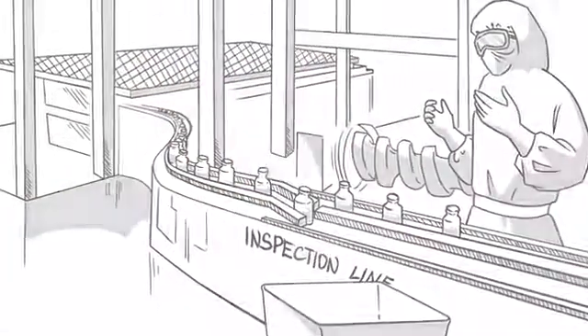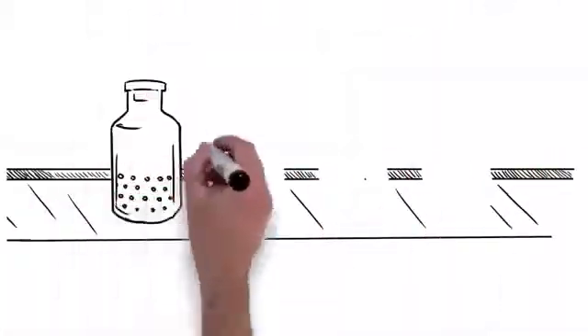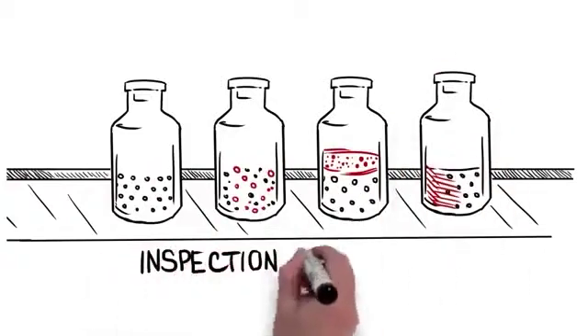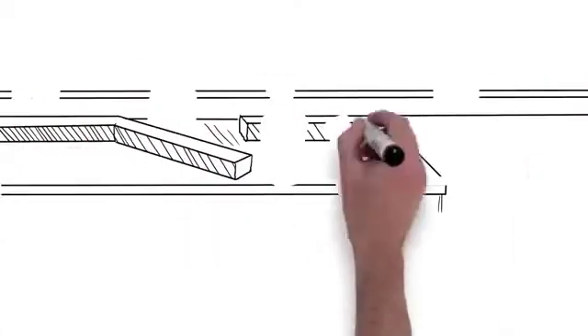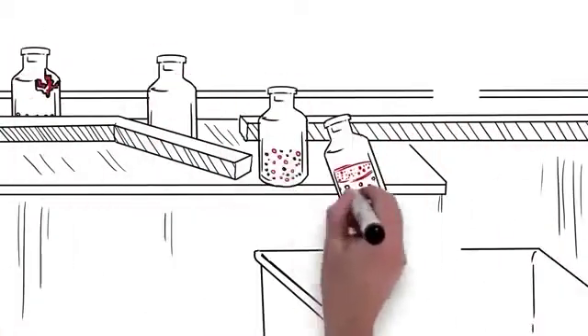but there have been some challenges. Vials are freezing at different rates and temperatures, and moisture content is varied. Some vials are showing evidence of collapse. As a result, product homogeneity and yield have been inconsistent.